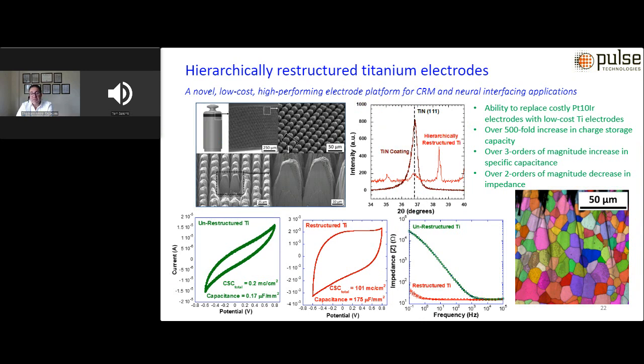So I'm really proud to say that we've developed a proprietary process that can hierarchically restructure high-performing titanium electrodes as a low-cost alternative to platinum-based electrodes. The technology offers numerous benefits over titanium nitride coatings that are traditionally used in CRM or cardiac rhythm applications as a coating on platinum-based electrodes. The technology has essentially redefined the CRM electrode technology because it offers many, many benefits. For example, in situ synthesis of high surface area titanium nitride, the low cost of the process, because it doesn't require the use of costly platinum iridium electrodes, but instead uses titanium. And unlike PVD-based titanium nitride coatings, it is a maskless process with no batch minimums, as I mentioned.